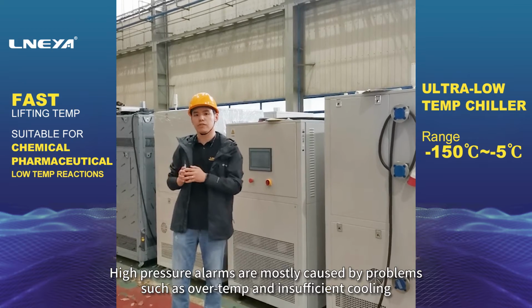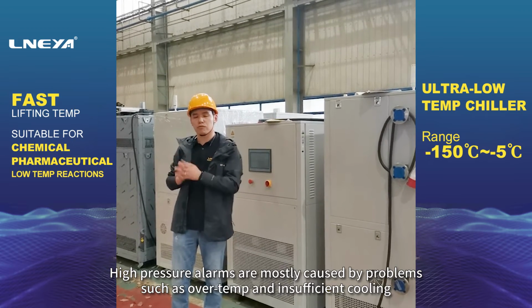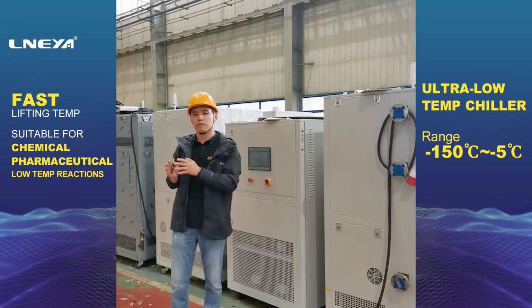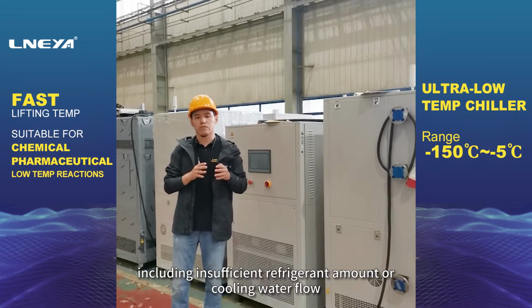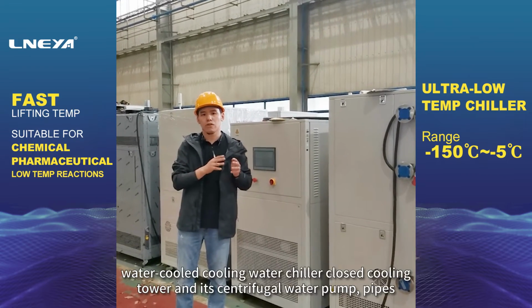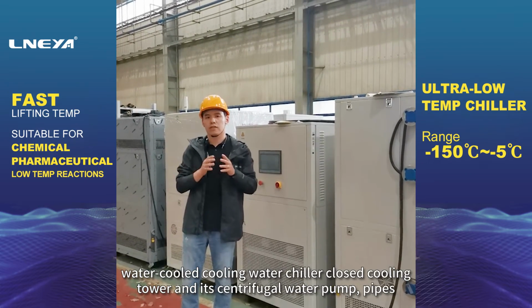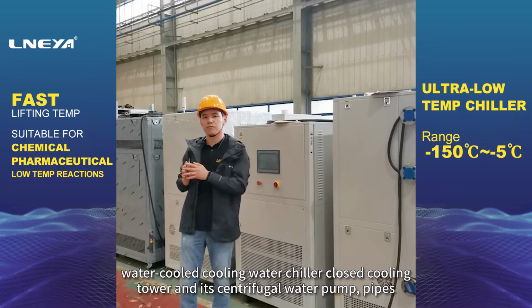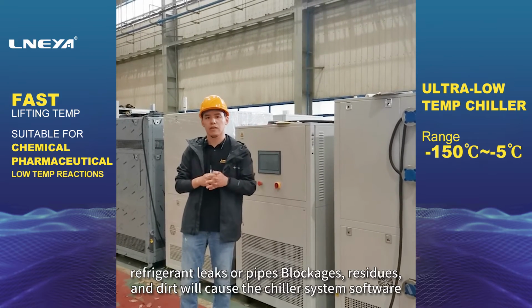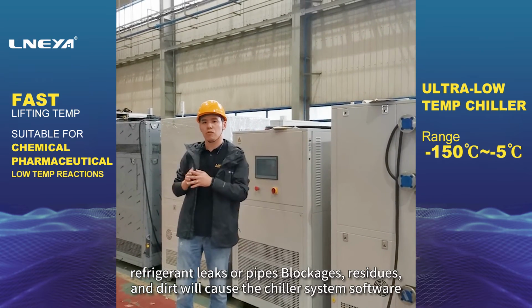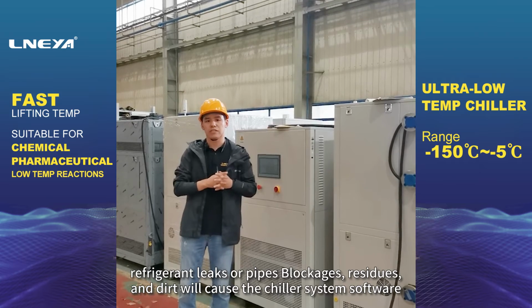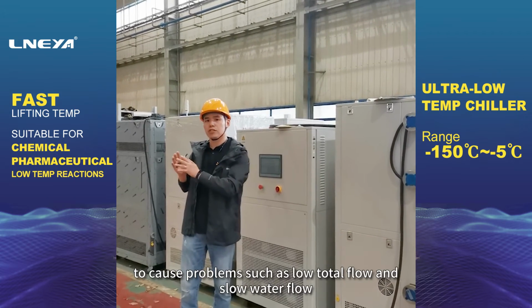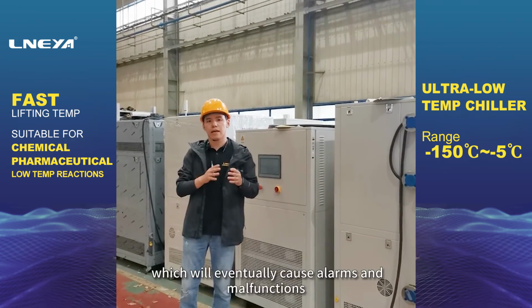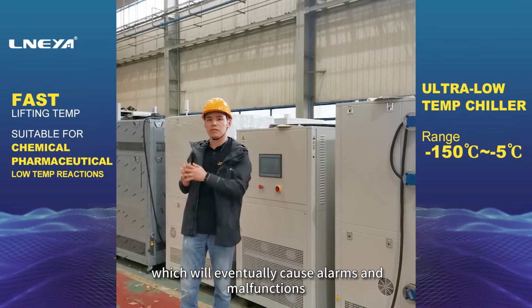High pressure alarms are mostly caused by problems such as overtemperature and insufficient cooling, including insufficient refrigerant amount or cooling water flow, the water-cooled chiller's closed cooling tower and its centrifugal water pump, pipes, refrigerant leaks or pipe blockages, residues, and dirt will cause the chiller system software to cause problems such as low total flow and slow water flow, which will eventually cause alarms and malfunctions.